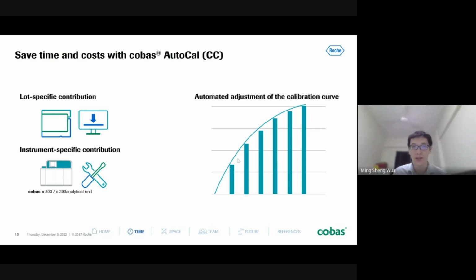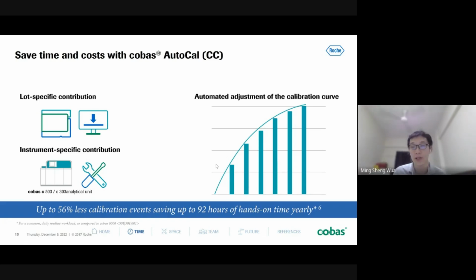How this works is that usually when we do a calibration, the calibration data consists of two portions. One comes from the reagent itself, what we call the lot specific contribution. The second part comes from the instrument itself. When we do an auto cal and download the data, the instrument specific contribution usually remains constant, unless we change a big part of the analyzer or do a big PPM. Other than this, what we are downloading is actually the data from the reagent. Combining these two data, the analyzer is able to automatically adjust a calibration curve for you. With this, for most of the clinical chemistry, the substrate and enzyme assays, you'll be able to do automatic calibration without the need for manual calibration. This will save up to about 56% less calibration, amounting to about 92 hours of hands-on time yearly.